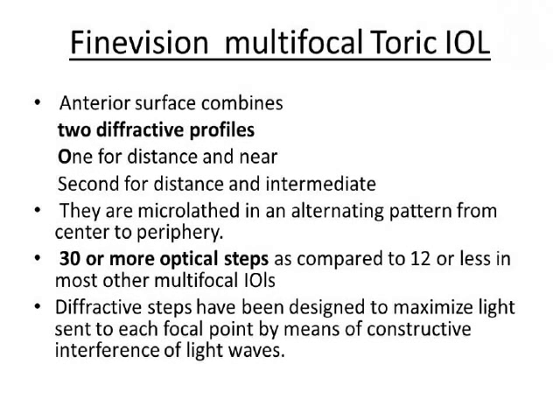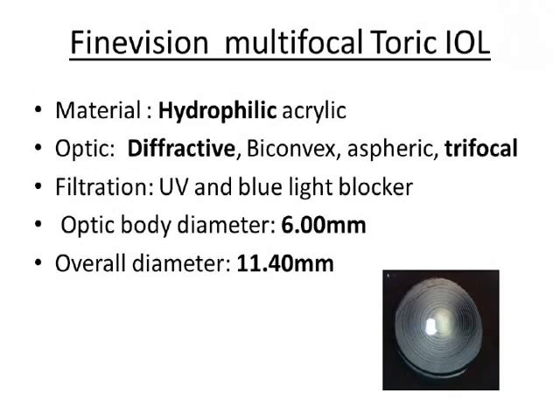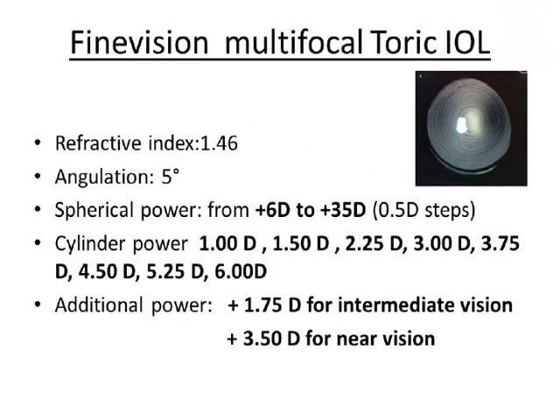The FineVision multifocal toric IOL has an anterior surface with two diffractive profiles: the first for distance and near, and the second for distance and intermediate. It has 30 or more optical steps, compared to 12 or fewer in most intraocular lenses, making it essentially a trifocal IOL. It is a hydrophilic IOL with diffractive technology, available in a 6mm optic and 11.4mm overall diameter, from +6 to +35 diopters spherical and +1 to +6 diopters cylindrical. Add powers are +1.75 diopters for intermediate and +3.5 diopters for near.